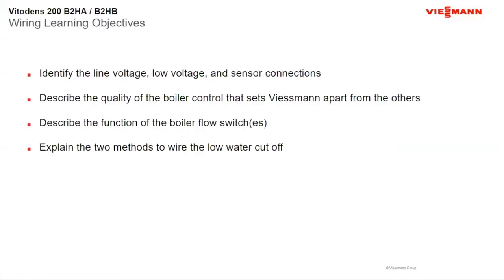Today's learning objectives: we're going to go over low voltage as well as line voltage, sensor placements, and note that all our sensors are auto-recognized — meaning once you plug them into the boiler, it knows it has them. We'll go over the quality of the controls that sets us apart, the flow switches and flow sensors — smaller models have flow switches, larger ones have ultrasonic sensors. We'll also cover a couple of ways to wire in your low water cutoff. In most cases, flow switches and flow sensors are approved as your low water cutoff.